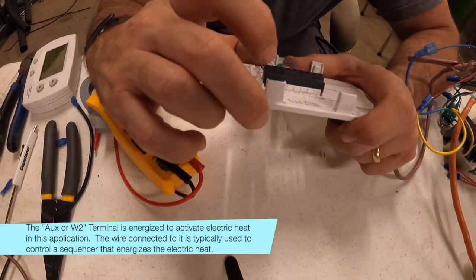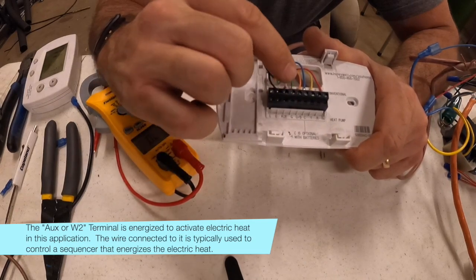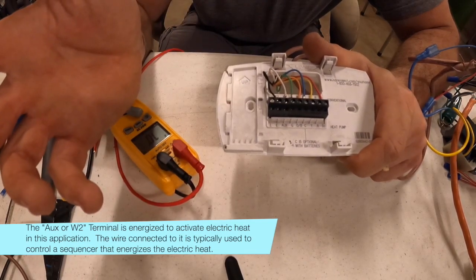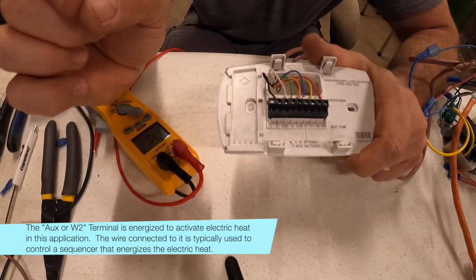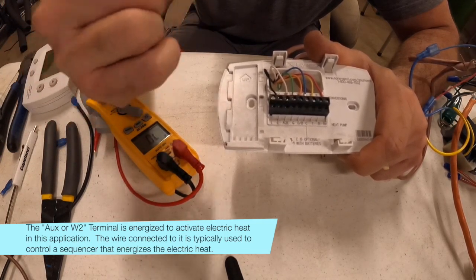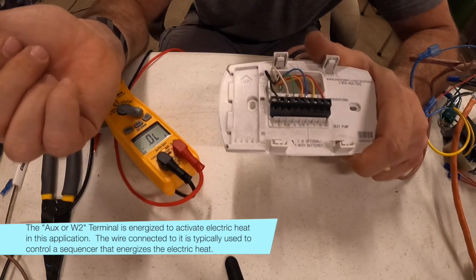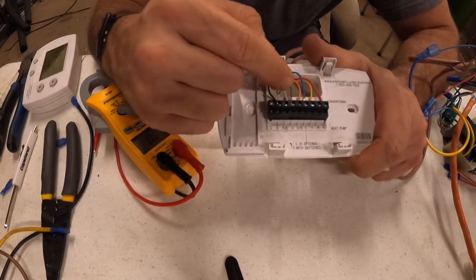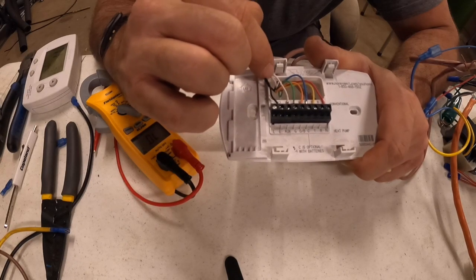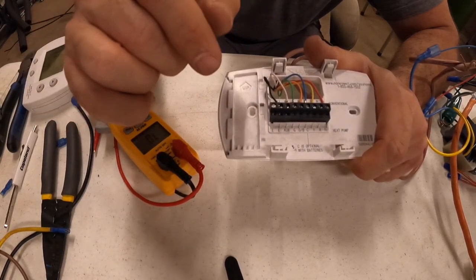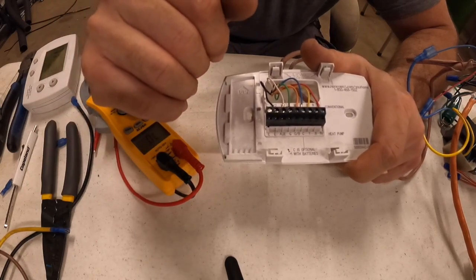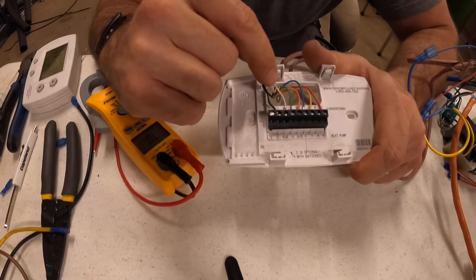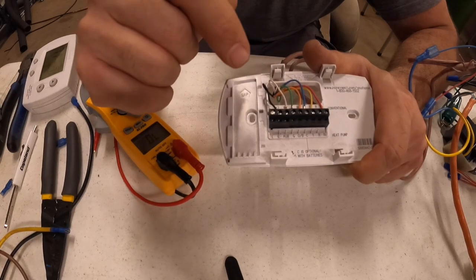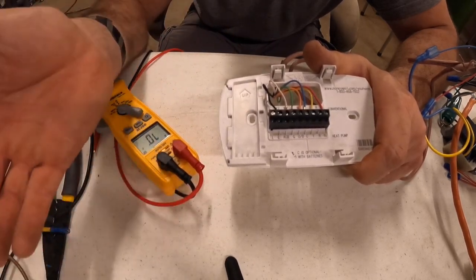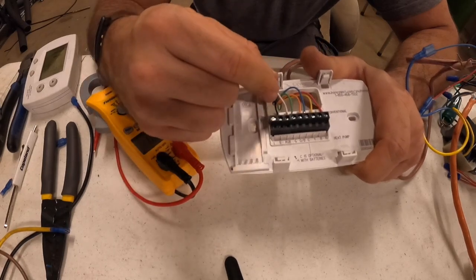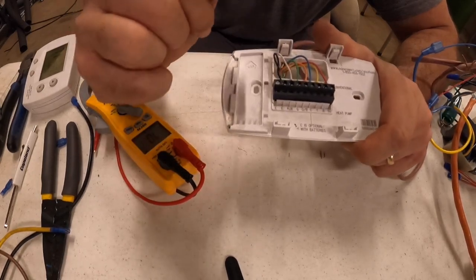All right, moving on to aux, auxiliary heat. When your heat pump can't keep up, or you see the auxiliary heat light come on the older thermostats, or you see auxiliary heat come on your digital thermostat, it's sending a signal, or providing 24 volts, to this terminal, which is going to be a sequencer, a relay, or a contactor to turn on the heat strips, which is your auxiliary heat in your indoor unit, or if you have a package unit, the heat strips in your package unit. And then E here is for emergency heat.